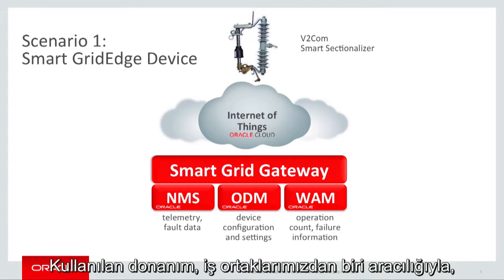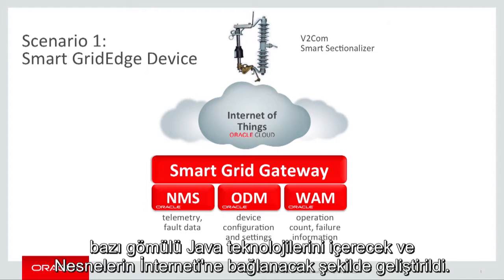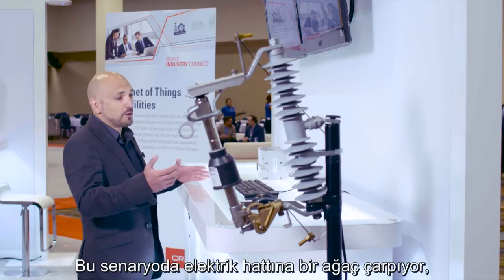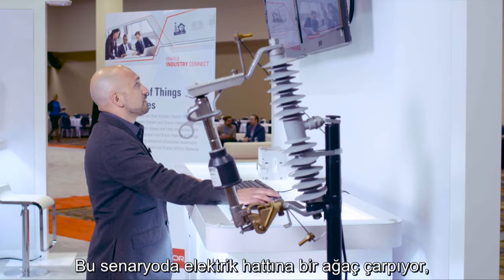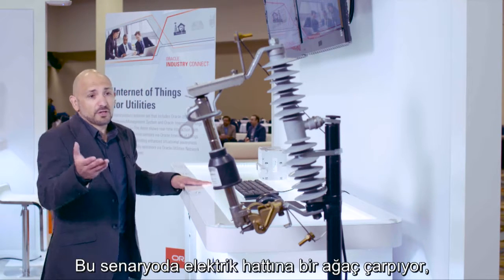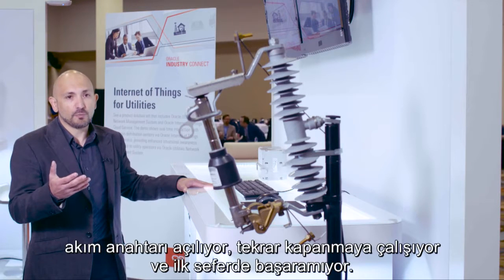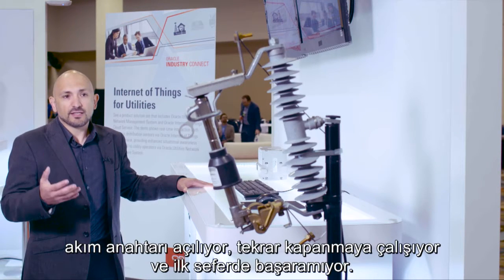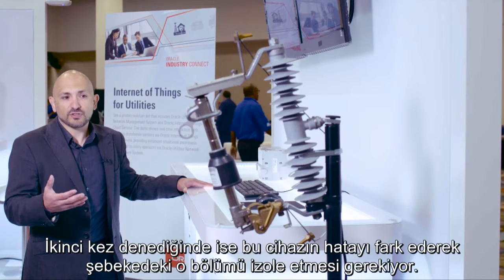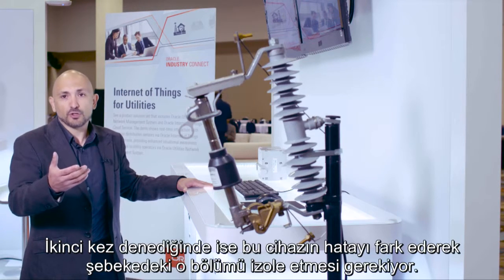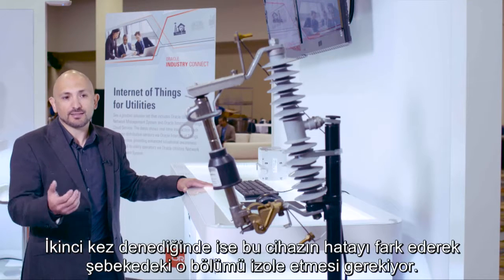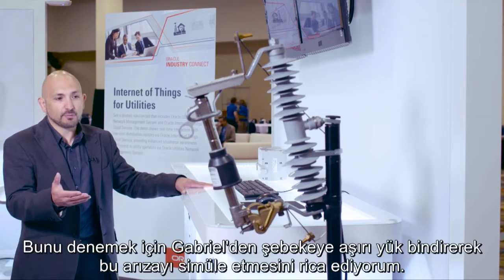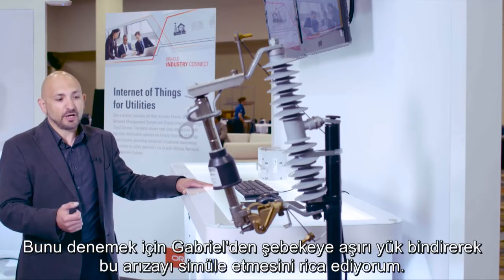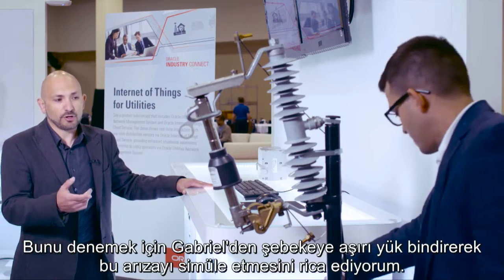Through one of our partners, the hardware has been enhanced to include some embedded Java technology and connectivity to the Internet of Things. So as part of this scenario, we have a tree hits a line, the circuit breaker opens, it tries to reclose, it doesn't hold the first time. As it recloses the second time, this device has been configured to open if it sensed a fault and isolate that section of the network. So I'll ask Gabriel to simulate a fault by injecting an overcurrent condition.